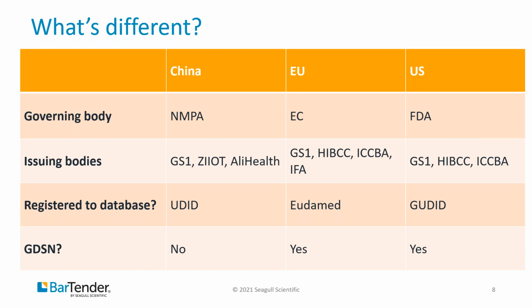A lot has changed in the past decade, and often I wonder if we're going to be reaching a time where the regulatory bodies will also require registration of the device identifiers, or the production identifiers. So it's only the device information, the static device data, the DI, that must be tracked and registered. Each regulating body has its own database for medical devices sold and used in its geography. In China, it's the UDI database, or UDID. In the EU, it's Eudamed, and in the US, it's the GUDID, or Global UDI database.